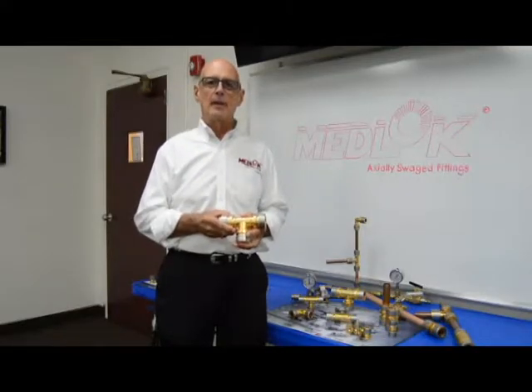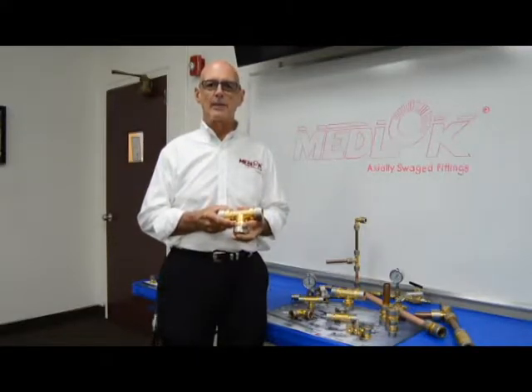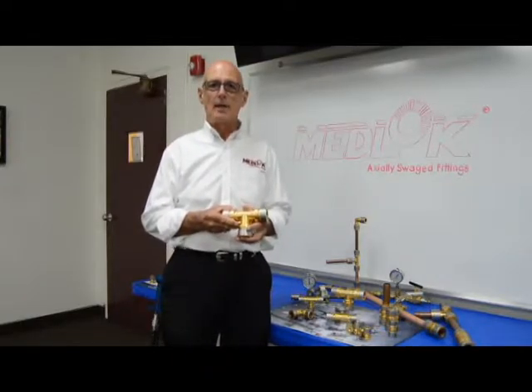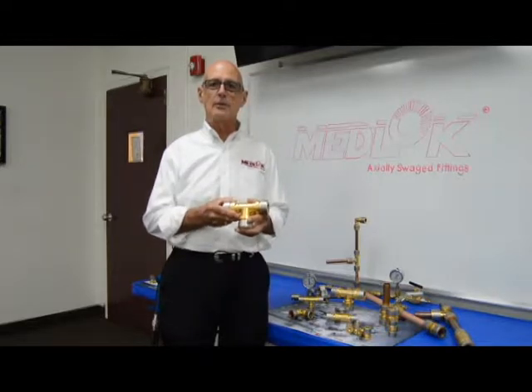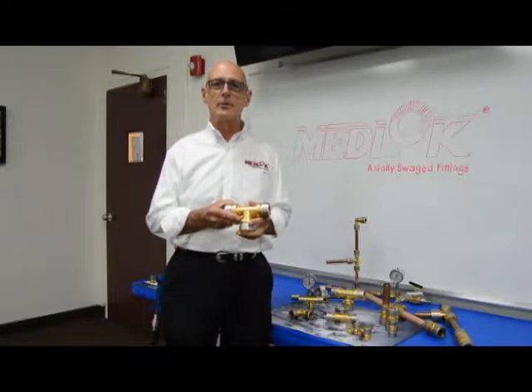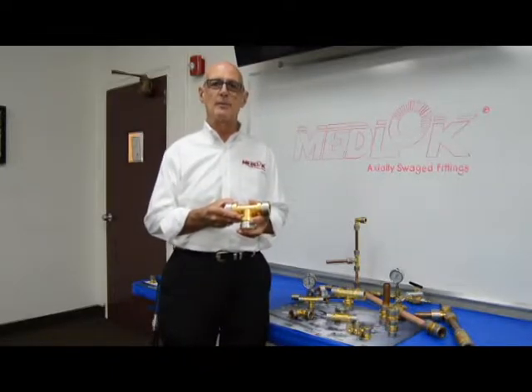I'd like to introduce a new patent-pending technology for medical gas fittings, which replaces braze joints and eliminates the need for hot work. The MediLok Axially Swaged Fitting was designed to meet the requirements of NFPA 99, Section 5.1.10.7.